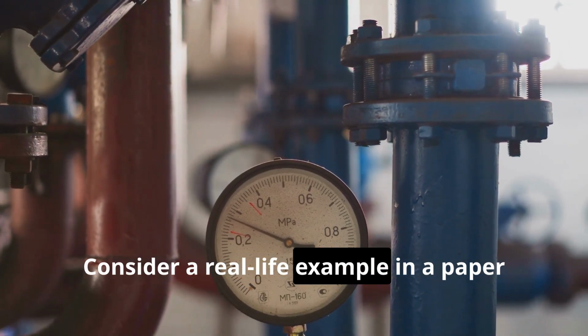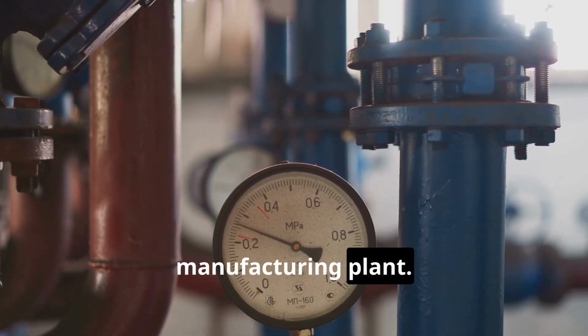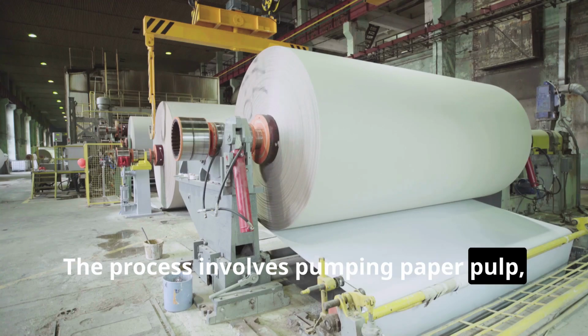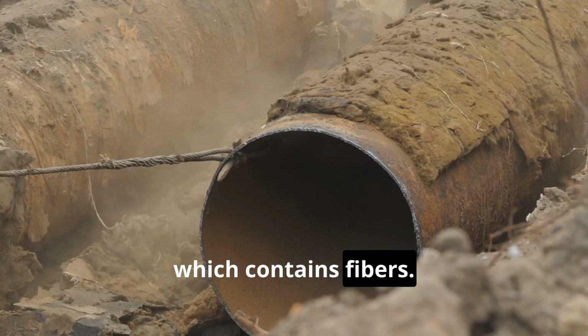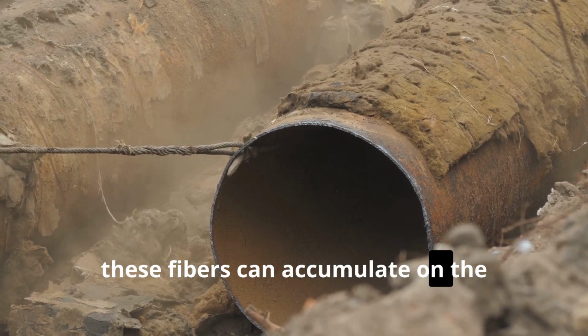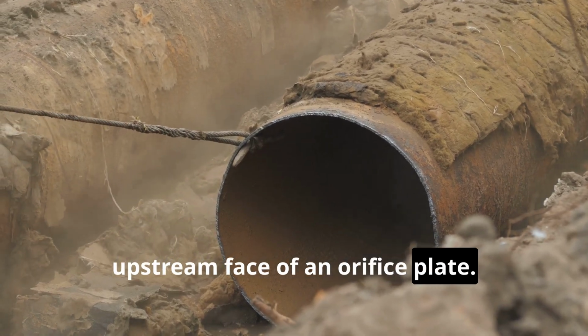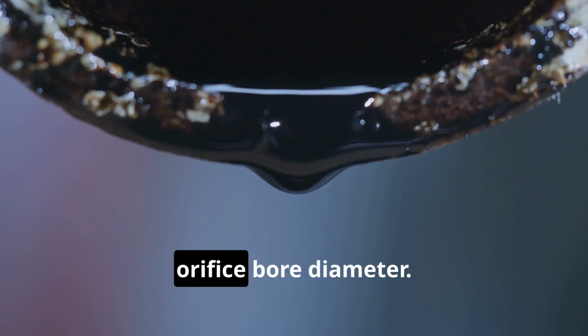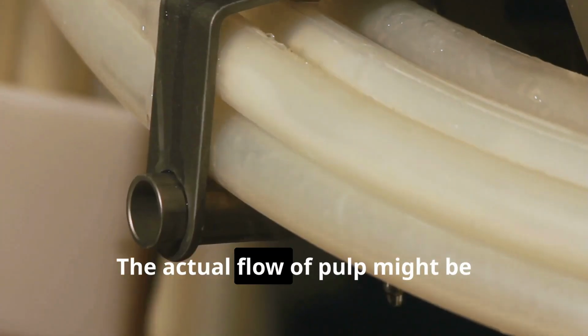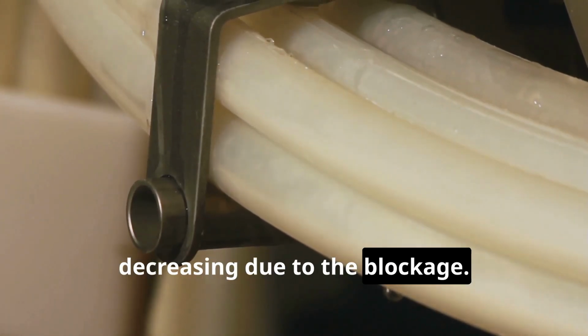Consider a real-life example in a paper manufacturing plant. The process involves pumping paper pulp, which contains fibers. Over time, these fibers can accumulate on the upstream face of an orifice plate. This buildup effectively reduces the orifice bore diameter. The actual flow of pulp might be decreasing due to the blockage.